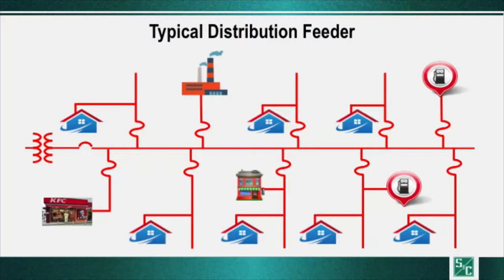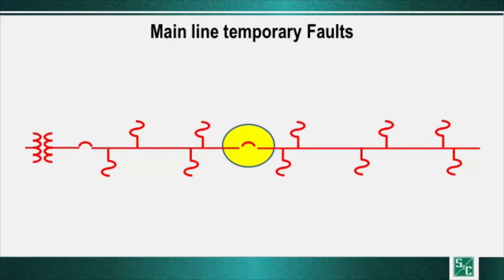If you talk to utilities, most will tell you that of the momentaries, about 20% come from the main line, and about 80% come from those laterals. So what FPL has done is on the main lines, they've started to add interrupting, reclosing devices in the middle, or in three sections of the main line.